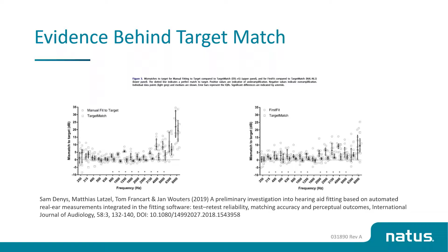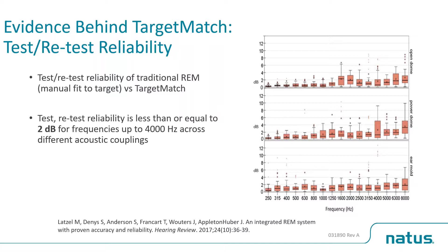Then if we look through here, you're going to see a little bit more data looking at the accuracy across different coupling measures. What they looked at is open fits versus power domes. And what you can see across all of these different couplings, and even the ear mold, is that there was still very little variability from the Phonak TargetMatch. So you can feel confident that no matter whether you're using a dome or an ear mold, the accuracy really doesn't change, and you're within about 2 dB up to 4000 hertz with these different couplings. So the test and retest reliability is very great with the Phonak TargetMatch. This information is published in the Hearing Review, September 2017, with the initial study coming out in 2016.